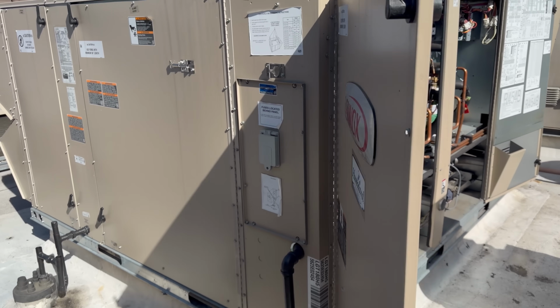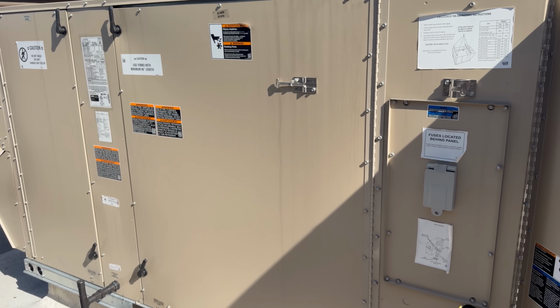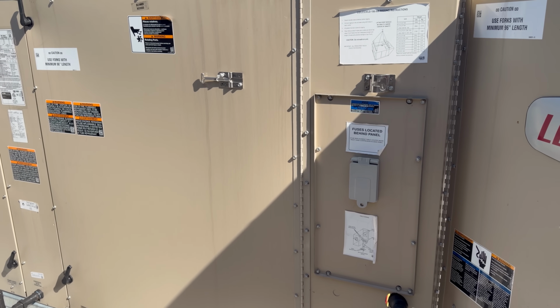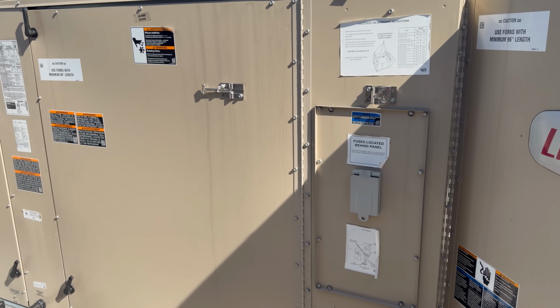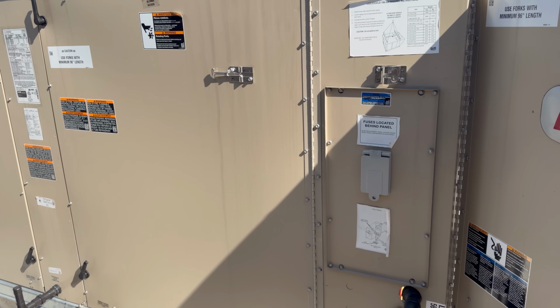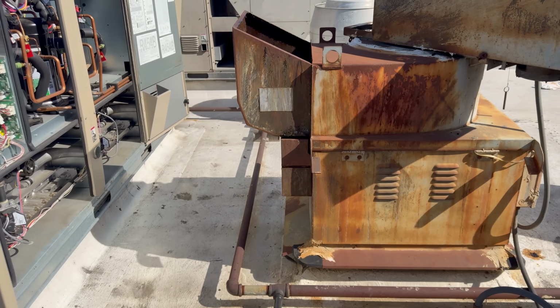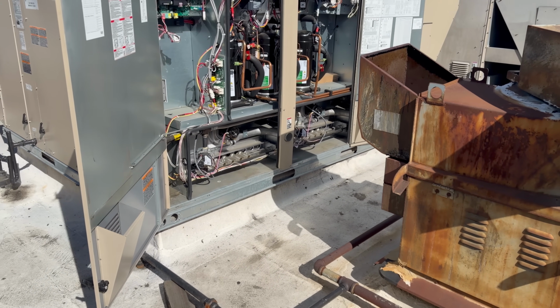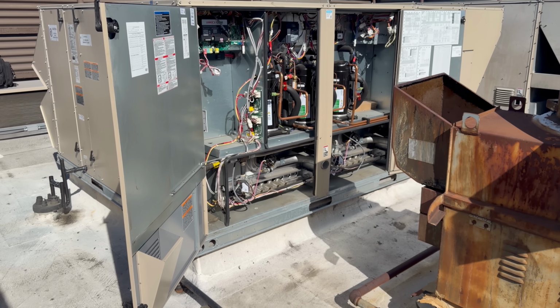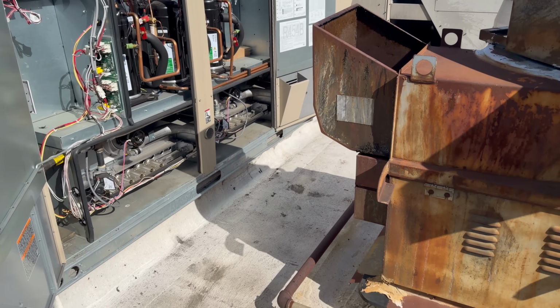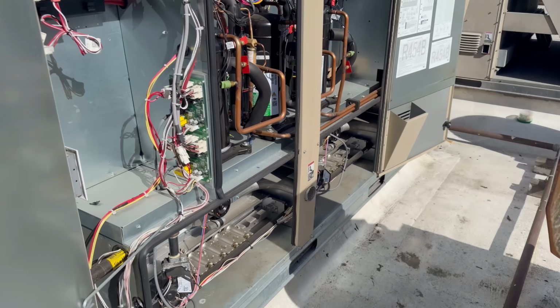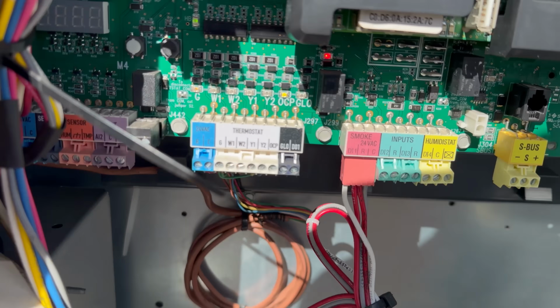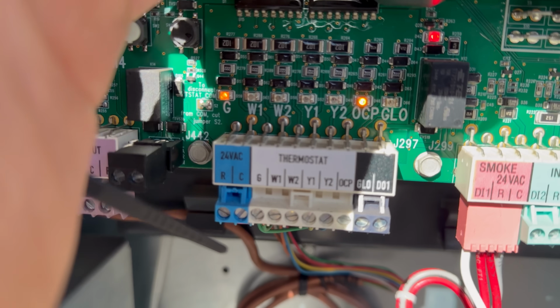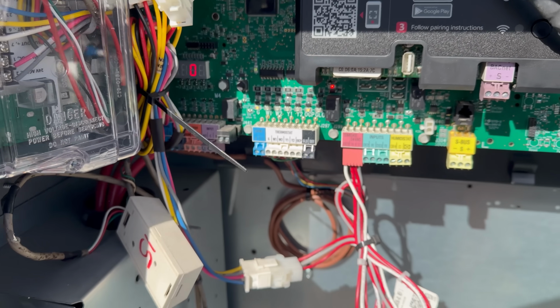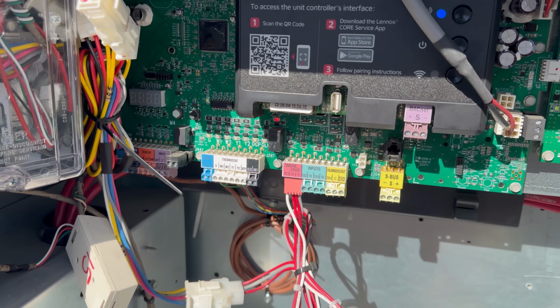We've got a kitchen AC today, and the complaint is that it's not cooling. They said it's hot. Today is February 27th. We're about to hit like 92-ish today. It's our first hot day of the year, and kitchen AC is not working. So when we walk up to the unit, you got to forgive the exhaust fan because it's right here. When we walk up to the unit, if you look right here, we've got a call for G and a call for occupied, but it's warm in the kitchen and we have no call for cooling.